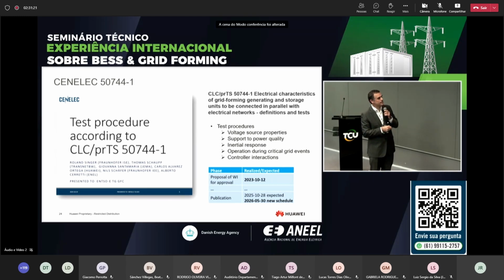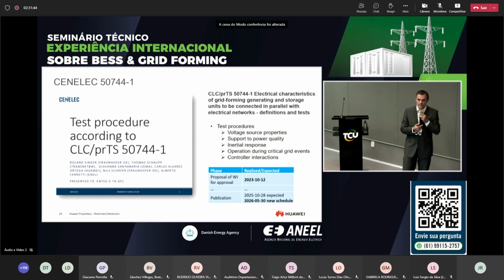So you can easily recognize this is European level. This is about how to measure the voltage source properties, how to measure power quality, mostly thinking about harmonics, inertia response, operation during critical events, mostly based on fault ride-through and frequency ride-through, and controller interactions. So the main point of this standard is how to measure in order to be able to compare different solutions.